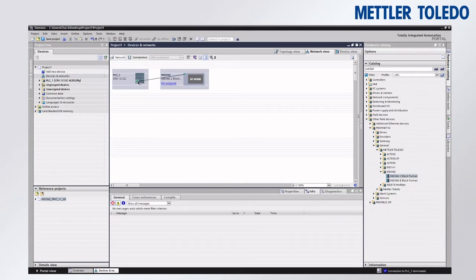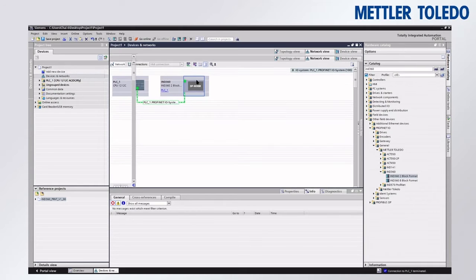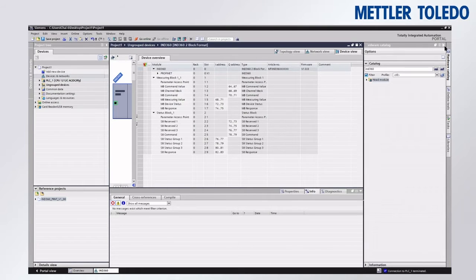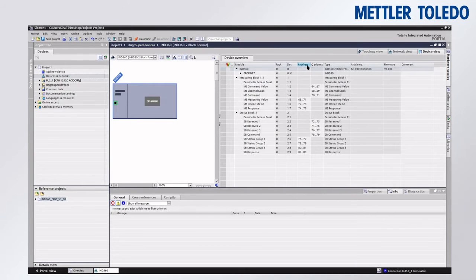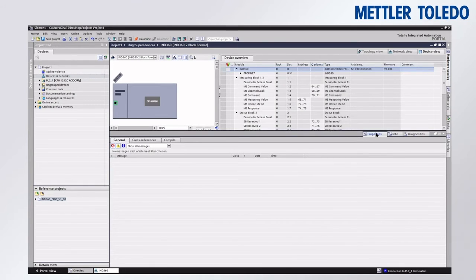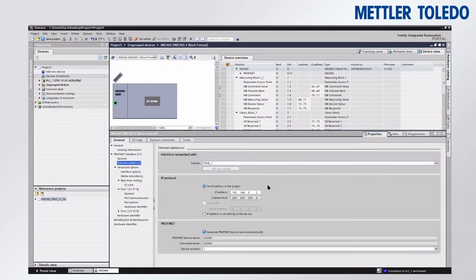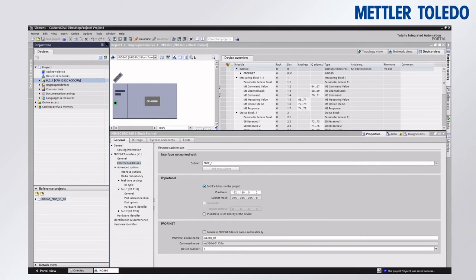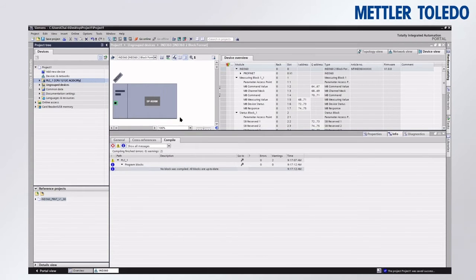We'll simply connect the IND360 to our controller and go into its settings. We can note the input and output addresses, which we'll come back to when configuring our PLC tags later. For now, let's go into the properties and look at the IP address. We'll also change the PROFINET device name to add an underscore zero one. Then we'll save the project and compile and download to our controller.